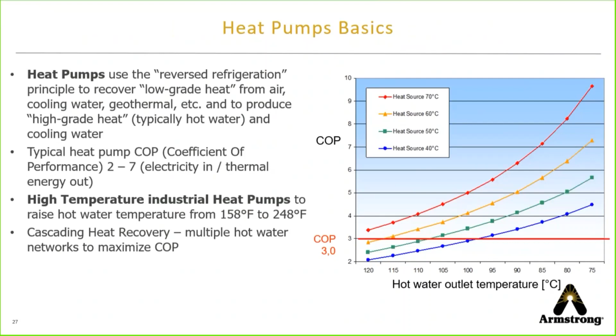And then we look at cascading heat recovery, because we have to keep the COP in mind. When we're taking a look through these studies, we're examining the heat sources we have and the temperature profile of those heat sources. Then, based on the refrigerant, what type of temperature we can get out of the heat pump, where it makes sense and keeps our COP in line with our requirements for ROI. So if we look at a heat pump, let's say we'll take 34 kilowatts of electricity in to generate 100 kilowatts of heat out.